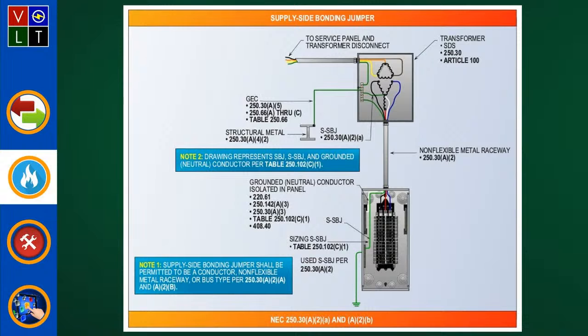250.102(C). Oh yeah, that's based on the size of the ungrounded phase conductors. If it's a bus type, then you have to pay attention to the cross-sectional area, not smaller than the supply side bonding jumper of the wire type per what? 250.102(C). So whichever type you're using here doesn't matter, but you're still going to have everything based on 250.102(C). Okay, gotcha. All right.